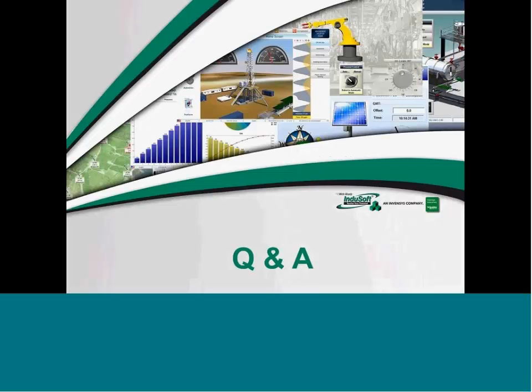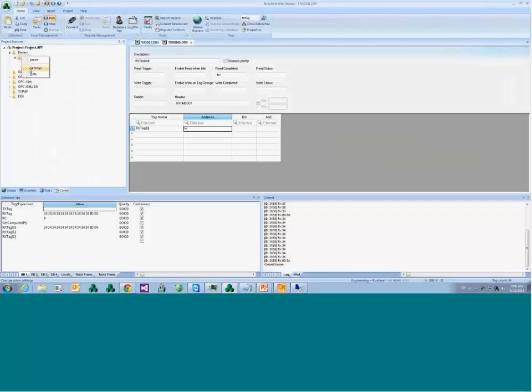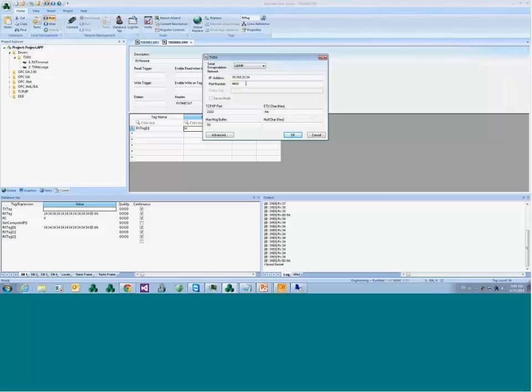Now I'm open for Q&A. First question: about communicating with more than one device using the pipe character in the TXRX worksheet. The pipe character is only used in UDP encapsulation mode — if you are going TCP/IP (serial encapsulation set to none) and want to communicate with multiple devices, you create separate TX worksheets for each, each with its own IP address and port in the Station field.